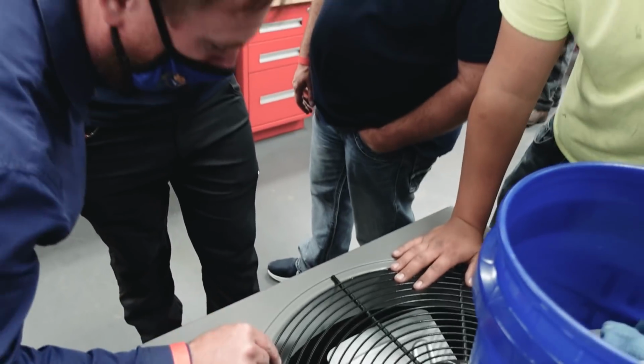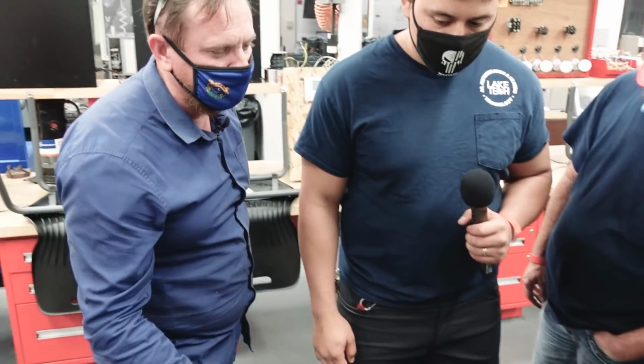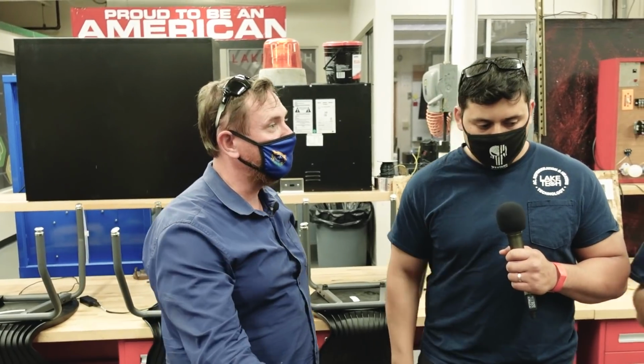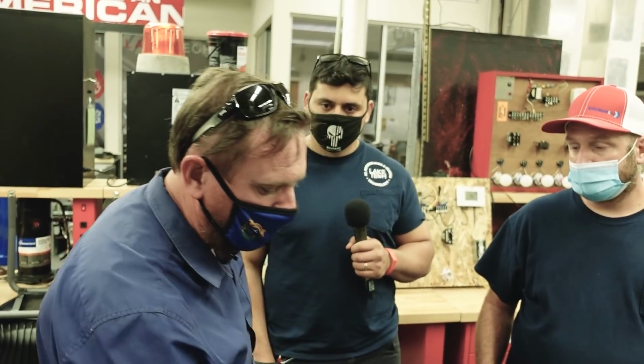What happens if those wires rub against one of those pipes? It's going to melt the insulation, or eventually rub the insulation off. It's going to be a direct short from that to the copper, or it'll even rub a hole in the copper. We went through about 4 calls this week with issues of rubbing where the wire rubbed out in maintenance. We ended up having to seal up that wire and make sure it wouldn't rub against the copper.